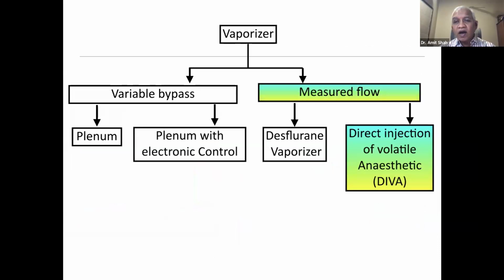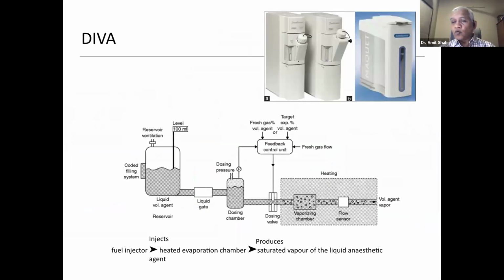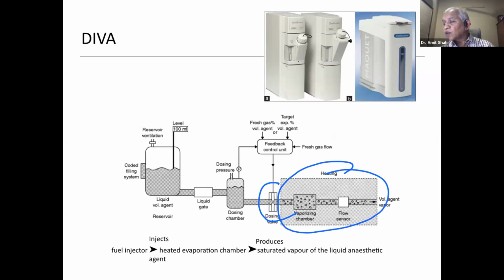There is something called the DIVA type of vaporizer, which is again a measured flow. There are two devices where it is used. One is, I think, the Aladin machine and one is the Maquet machine. These are the two vaporizers where what the vaporizer does is that the liquid agent is made into a vapor. It goes into a dosing chamber, then goes into the vaporizing chamber where vapor is made from that fixed amount of liquid.